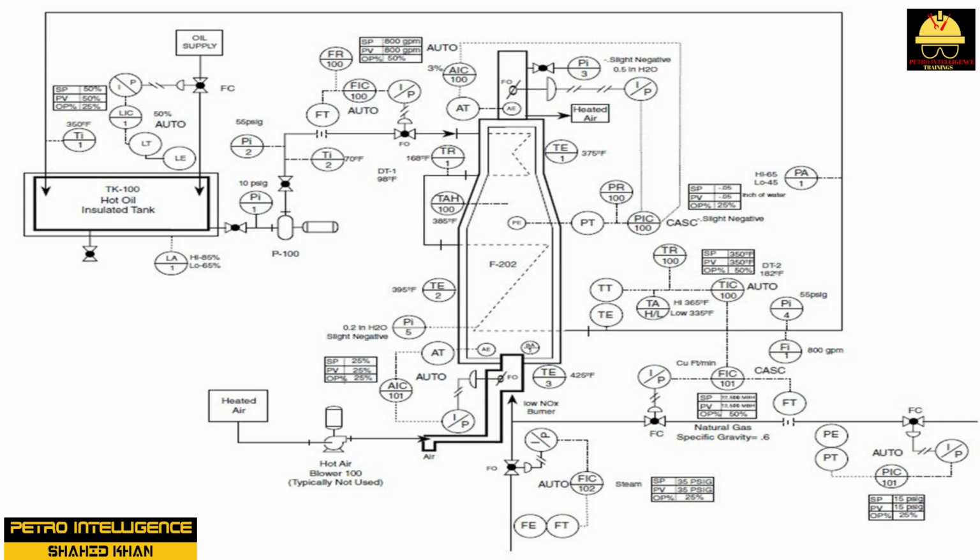F-202 is a clean operating system that keeps excess airflow between 8 and 10%. Ensuring proper air-fuel concentrations is critical to efficient furnace operation because the fuel burns cleaner and hotter. Incomplete combustion reduces heat output, produces waste gases, and creates a potentially hazardous condition as unburned fuel collects in the firebox. Efficient, safe process heater operation requires a technician to carefully observe and control the combustion process.